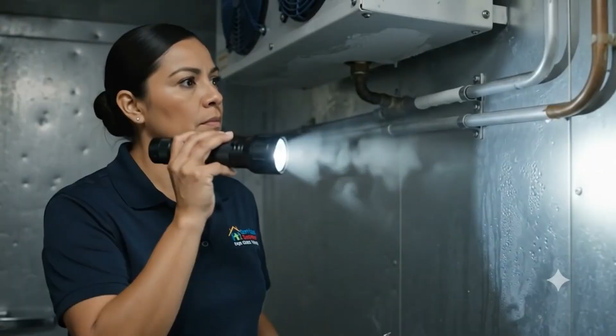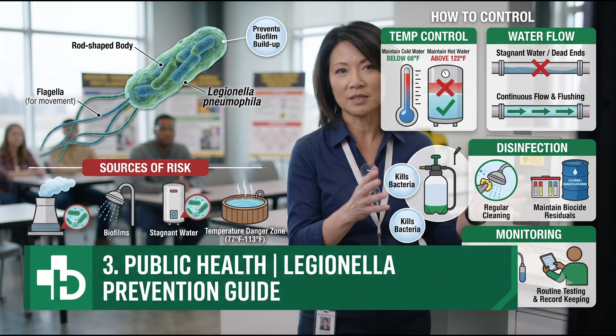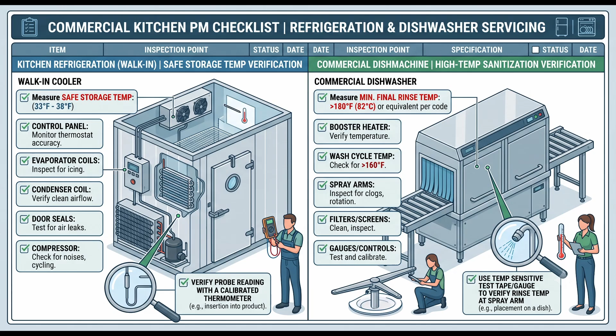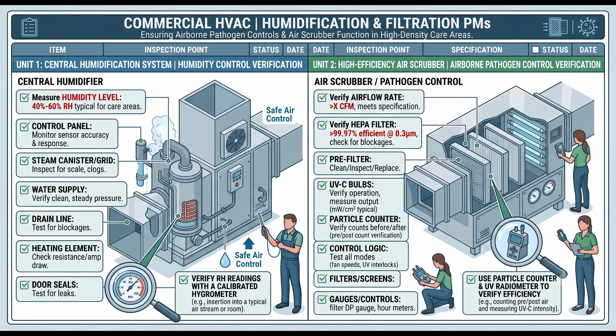Entity number 3, the Health Department. Their primary focus is environmental sanitation, food safety, and infection control. Your Health Department PMs must cover daily and weekly domestic water temp logs, balancing hot water so it's high enough to prevent Legionella growth, but controlled below scald and burn thresholds at the faucet. Kitchen refrigeration and dishwasher servicing, verifying that walk-ins hold safe storage temps and commercial dish machines reach high-temp sanitization levels. HVAC, humidification and filtration PMs, ensuring air scrubbers and airborne pathogen controls function properly in high-density care areas.